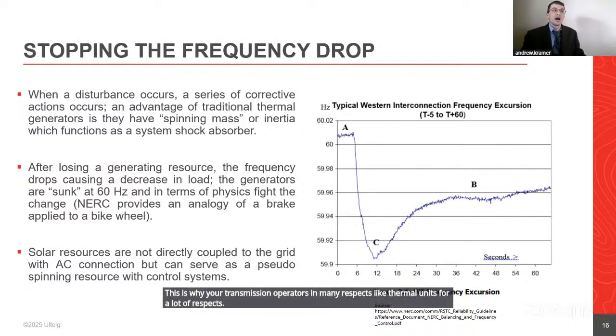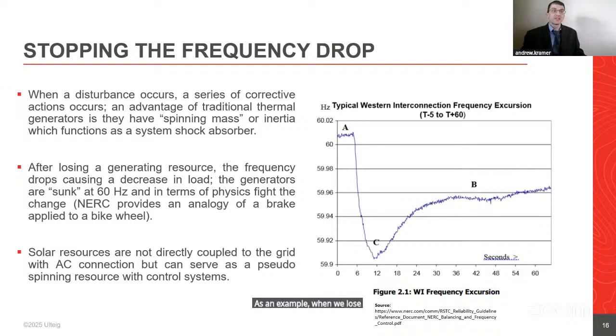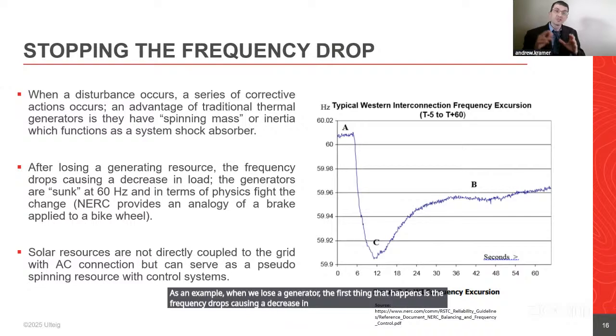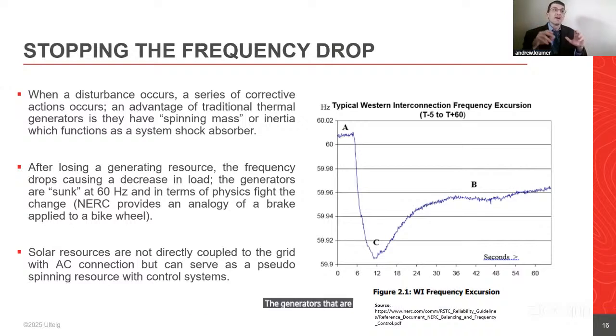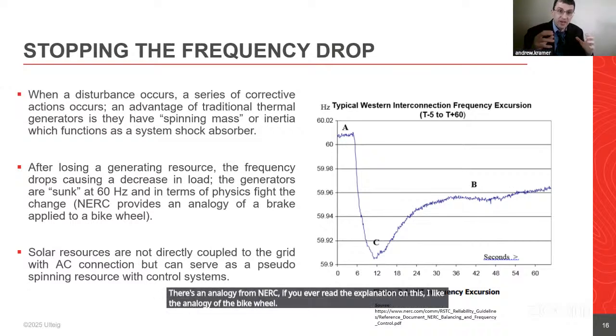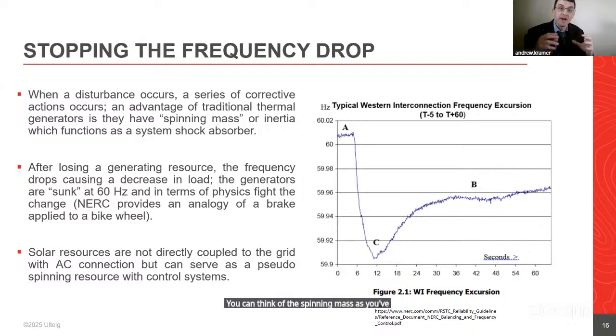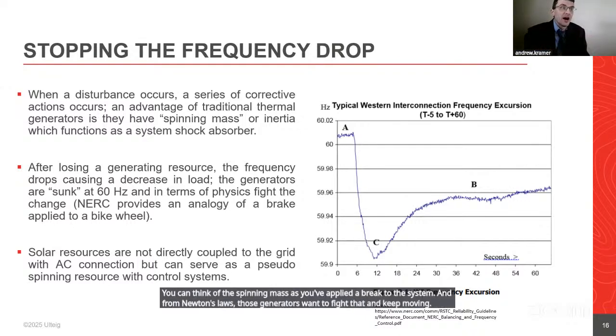As an example, when we lose a generator, the first thing that happens is the frequency drops, causing a decrease in the load. The motors and everything else see that drop in frequency, and they're going to start having issues and dropping some of their load. The generators that are synced into the system fight this change. There's an analogy from NERC. If you ever read the explanation on this, I like the analogy of the bike wheel. You can think of the spinning mass as if you've applied a brake to the system, and from Newton's laws, those generators want to fight that and keep moving.